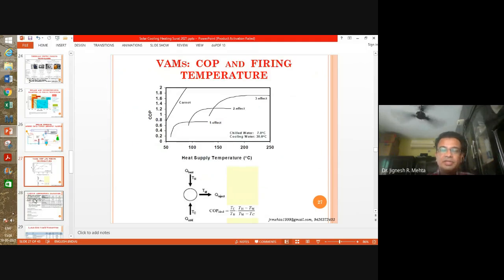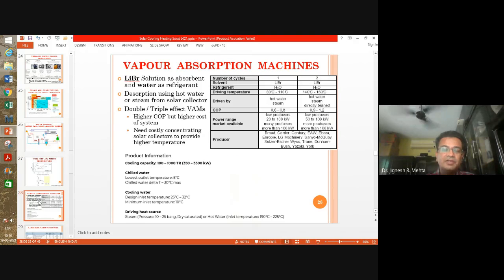Okay. Now, what this graph is showing is, the higher the driving temperature, you can get more COP by switching from single effect to double effect and triple effect. But of course, this will increase the cost of the chiller. It will also increase the required temperature from the solar collectors. So the investment cost of the solar collectors will also rise. And there have been efforts.